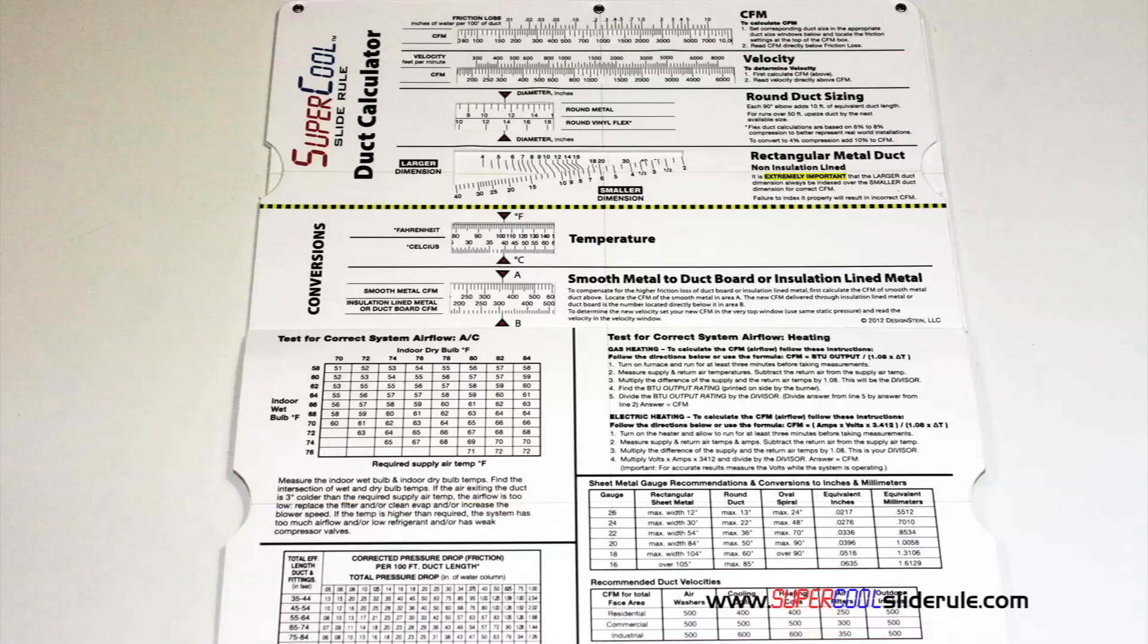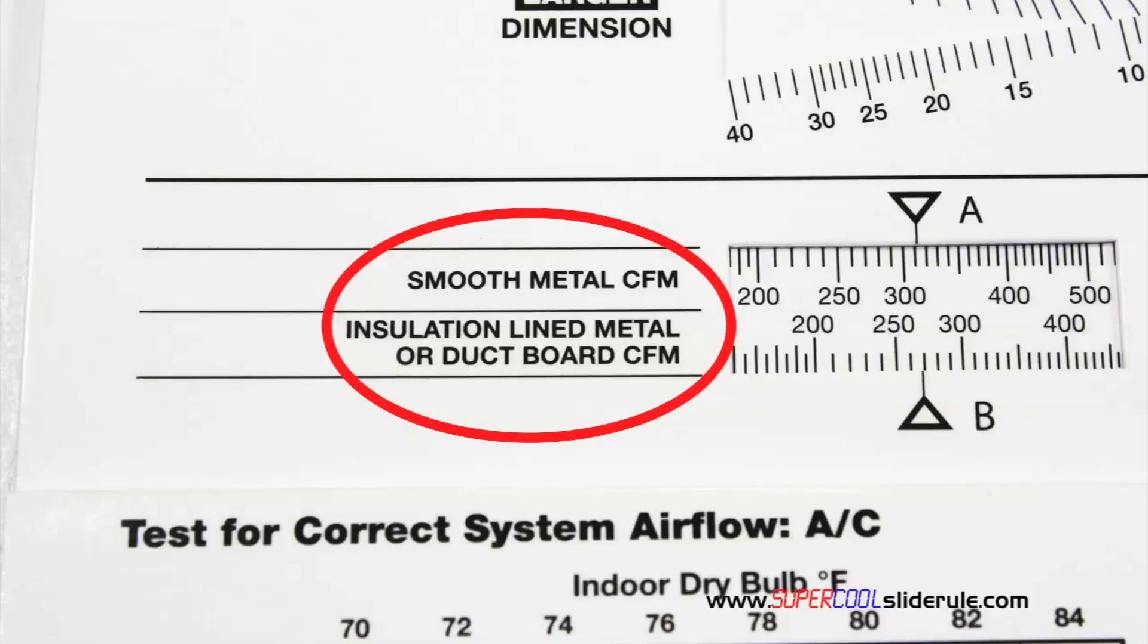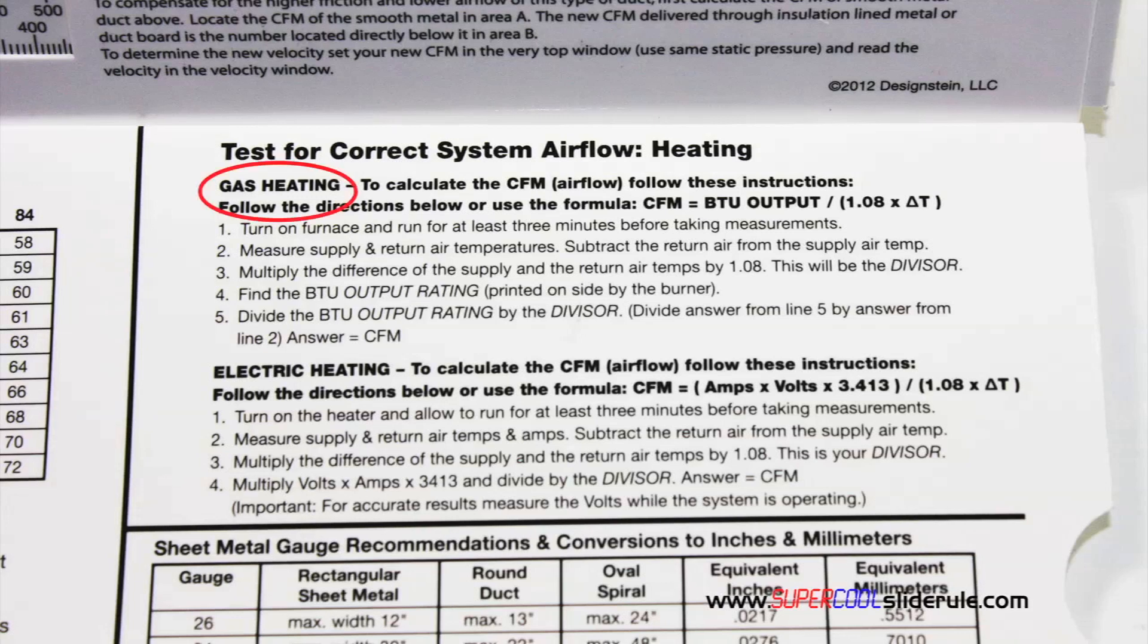Inside, it is packed with even more information. It performs sizing of both metal and flexible duct. It has the only direct reading conversion from smooth metal to insulation lined metal we've ever seen. The majority of technicians have never been taught that if the insulation is on the inside of the ductwork, you cannot size it with a regular duct calculator.